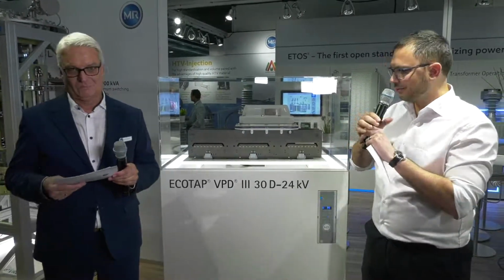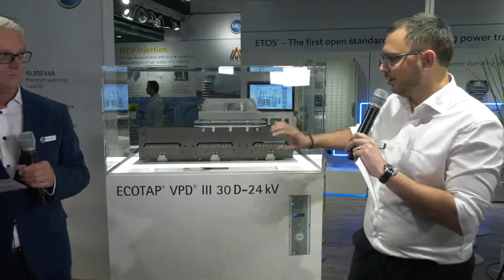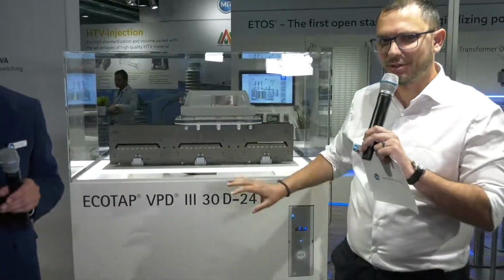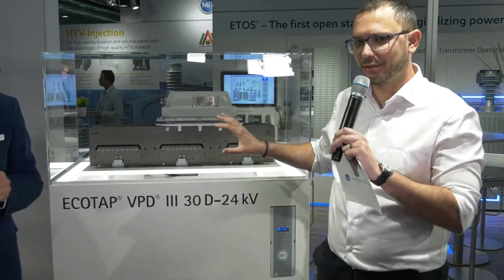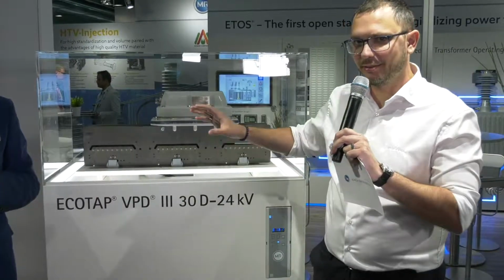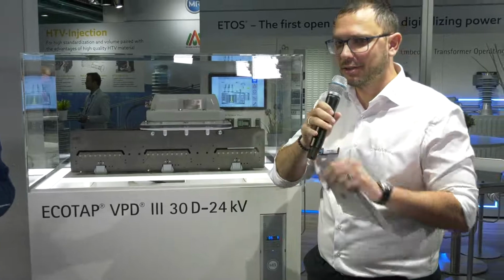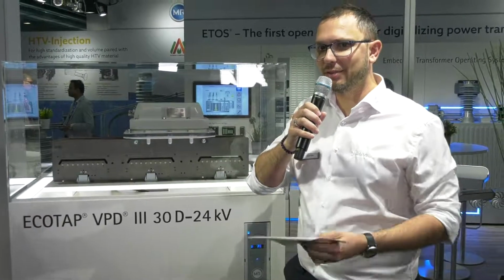The one you see behind me is composed of 3 main parts: the OLTC itself, the black part; the motor, the gray part; and the controller. The motor and controller are 100% identical across all versions of this model—only the OLTC, immersed in oil, changes. With different versions we can go up to 100 amps, up to 40.5 kilovolts, and we can also offer 17 positions. This one is a 9 position.